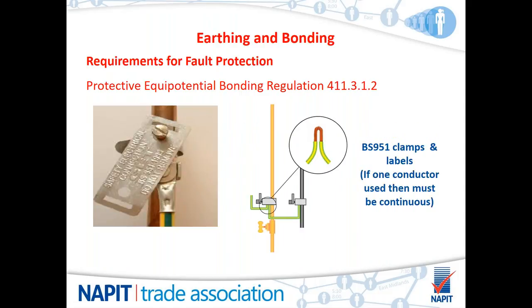Okay, so when bonding your gas and water, you should be using the BS 951 clamps and labels. Now, these labels essentially say safety electrical connection, do not remove. You may choose to bond your gas and water separately, or alternatively, you could use one conductor so long as this conductor is continuous, i.e., you don't get to the water, cut it, then go to the gas.